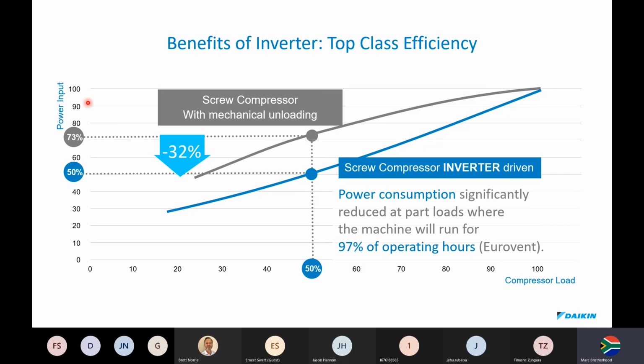So if we look at this chiller's power inputs, a screw compressor with mechanical unloading uses up to 73% power. But for the screw compressor which is inverter driven, if we look at this linear line on the graph, power consumption is significantly reduced at part load, where the machine will run for at least 97% of its operating hours. So what does that mean?